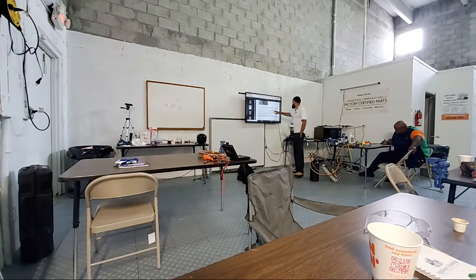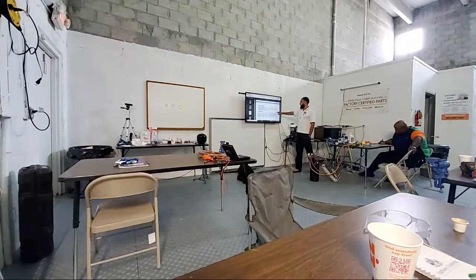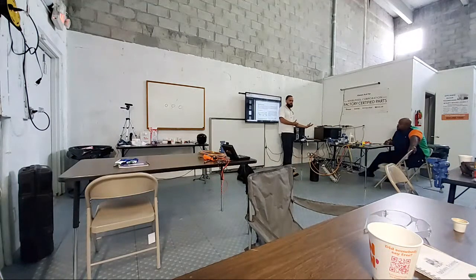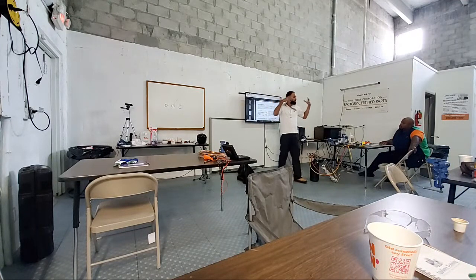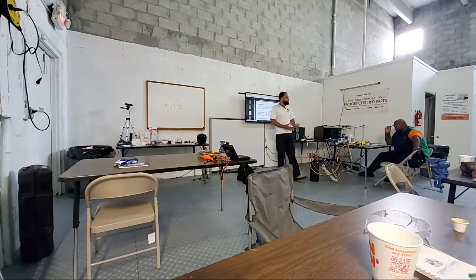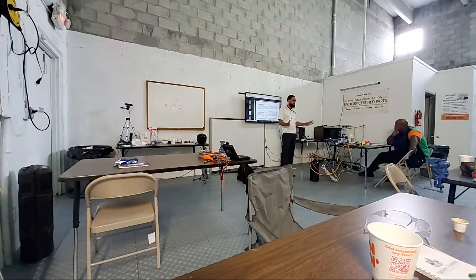Okay, 6 to 8 hours, okay. I'm just gonna skim through this and read you the important stuff. It's important to read this, guys. Okay, but that's one style. The adaptive uses door opens. How many times was the door open? How long was it in defrost the last time? How long was the compressor running? It's adaptive, it's using all of this information to determine a cost-efficient defrost time. If it's 8 minutes, 30 minutes, an hour, it's adaptive based on all the information that it receives. That's it, in a nutshell.